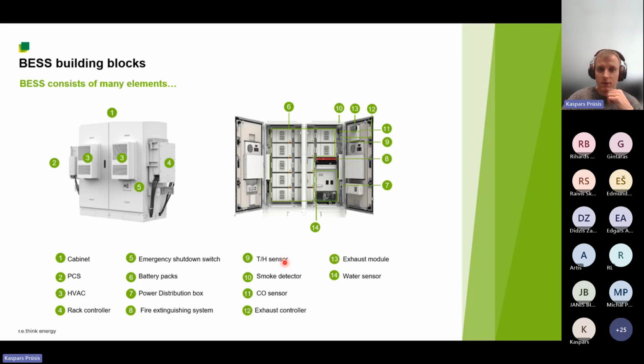And also we have multiple sensors, for example, temperature and humidity sensors, smoke detectors, CO sensors. Also for this particular system, we have an exhaust system, which means that if you have issues with the batteries and they start to produce gases, these gases can be released outside into the atmosphere, reducing the possibility of fire in this battery storage. And of course, there's a water sensor. By this, I wanted to emphasize that these systems are complex, consisting of multiple elements, and each of these elements has a specific role in the good operation of such a system.